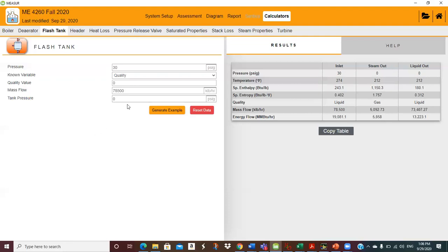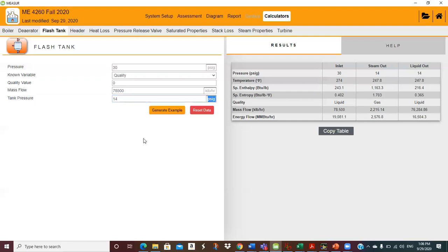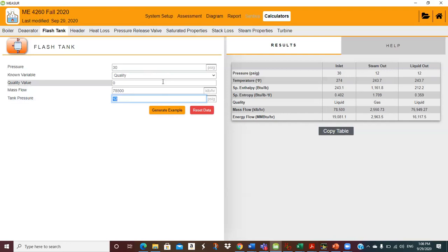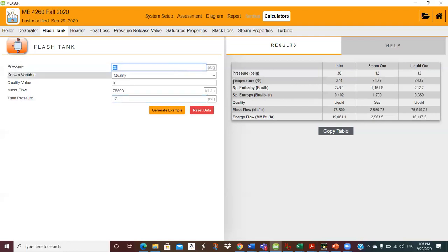What if I just basically had a pressurized tank and piped that steam into the de-aerator? It might have to get to 13 or 14 pounds before it had enough pressure to get in there. Let's say I take it to 14 — I've still got 2,215 pounds. If I said 12, I'm getting 29. But here's another issue: this is assuming that the condensate is saturated at 30 PSIA. I'm not saturated — I'm only at 240°F. There might be a little hitch here.